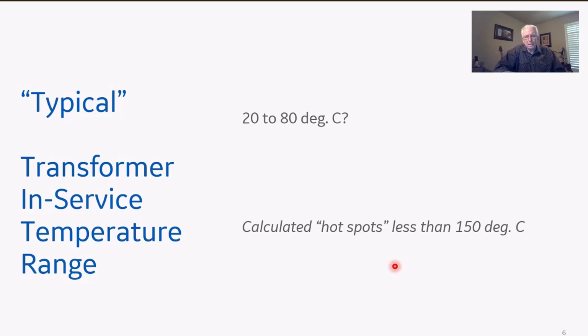Since these temperatures begin generating at 150 degrees C from a thermal standpoint - and I keep saying thermal because we're going to talk in a minute about partial discharge, which can generate well below 150 degrees C - these calculated hotspots in transformers, looking at where a transformer operates for its life and where it should be, you're not going to be hitting the 150 degrees C mark. For one thing, paper can't take 150 degrees C. Kraft paper can't, not for any length of time. It can take it for a little bit, but if nothing's done about it and it stays there, ultimately it's going to destroy the paper.